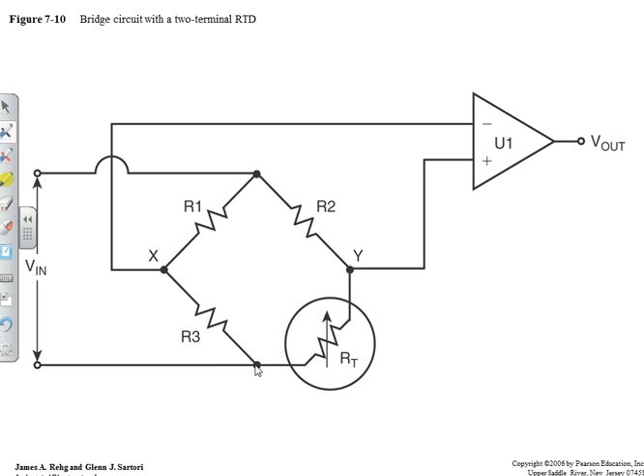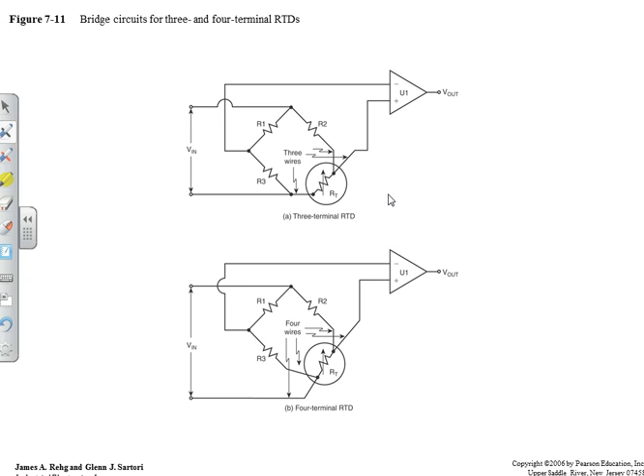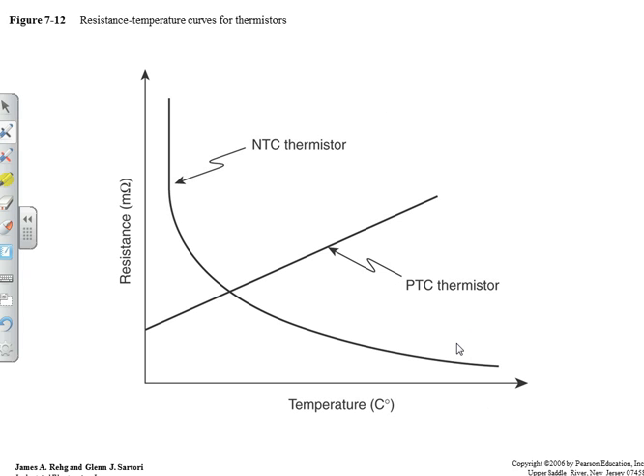These wires are short, in my cabinet, very close to each other. This guy might be 500 feet away, sensing something a long ways away, sending the wires back. I'm doing it again, what's the difference? Three wires are hooked up and four wires are hooked up. I really don't see any difference there, except I brought a wire into where the sensor is instead of into the bridge. I'd probably rather do it in a 3-wire terminal than a 4-wire terminal, because that looks like too much copper. It would cost me more to hook up.